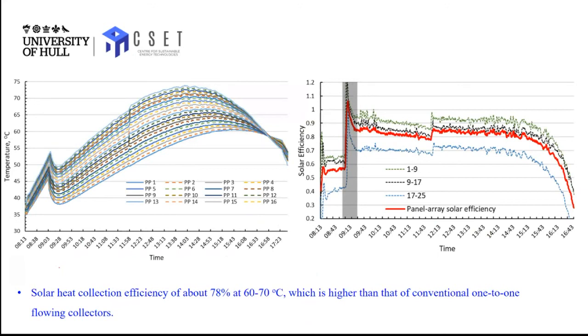On the right side, it shows the correlation between solar efficiency and time for different panel numbers, and the efficiency variation of panel 8 during the daytime. Our test results show that at an operational temperature of 60 to 70 degrees Celsius, the solar efficiency of the panel array achieves around 78%, which is higher than a traditional one-to-one connected solar panel array.